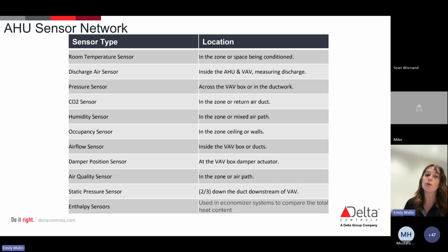But you'll see things like room temperature sensors, CO2 sensors, humidity sensors, occupancy. Occupancy is going to be one of those that is going to trigger something in everybody's minds after we're done here. I'm going to say, oh, occupancy, we might need to increase ventilation rate just because we have standards in play. And then the only other one that I really want to point out is that static pressure switch. Just for peace of mind, what everybody says is it should be located about 2/3 of the way downstream of the VAV. And that's what's really going to pull in that air or slow down the air by the VFD.